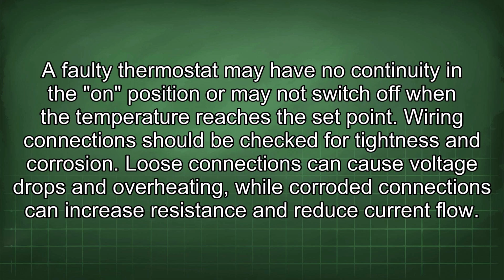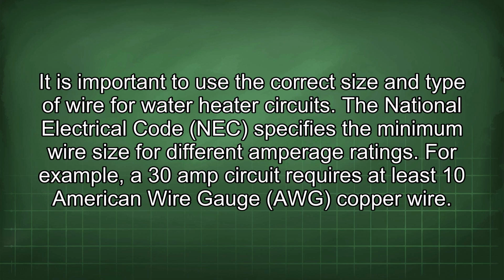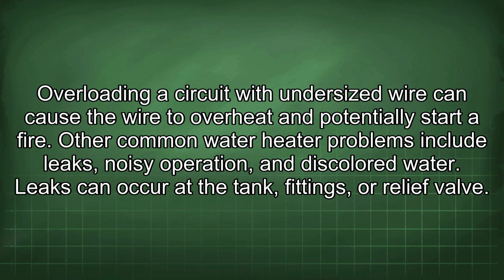A faulty thermostat may have no continuity in the on position or may not switch off when the temperature reaches the set point. Wiring connections should be checked for tightness and corrosion. Loose connections can cause voltage drops and overheating, while corroded connections can increase resistance and reduce current flow. It is important to use the correct size and type of wire for water heater circuits. The National Electrical Code (NEC) specifies the minimum wire size for different amperage ratings. For example, a 30 amp circuit requires at least 10 American wire gauge (AWG) copper wire. Overloading a circuit with undersized wire can cause the wire to overheat and potentially start a fire.